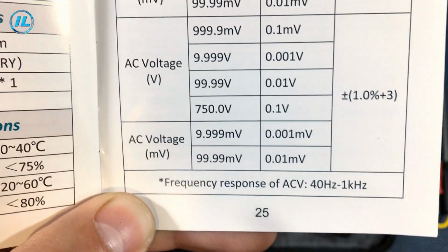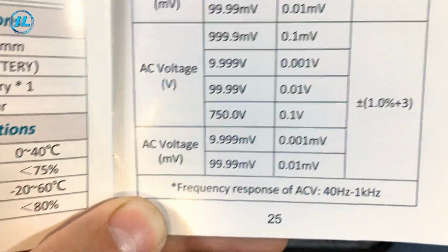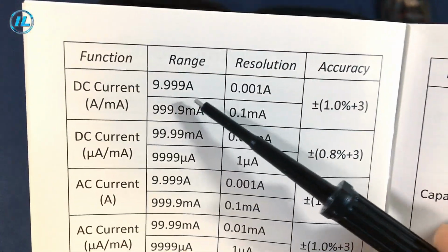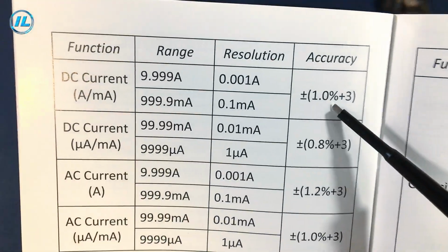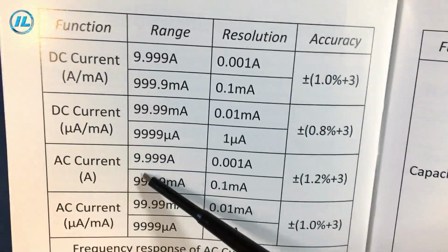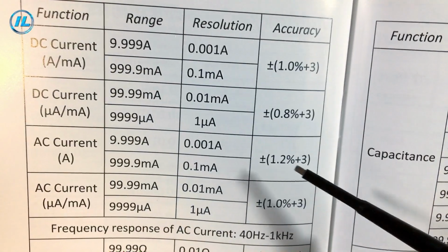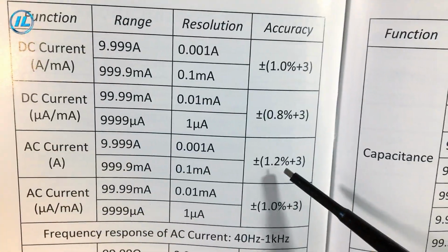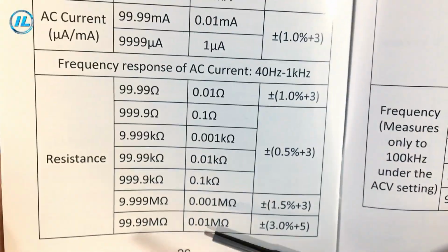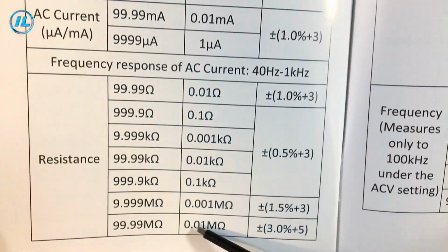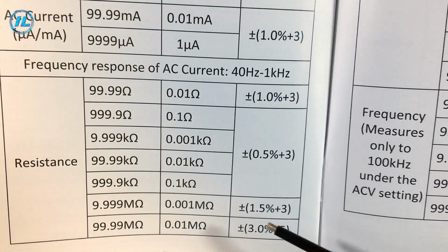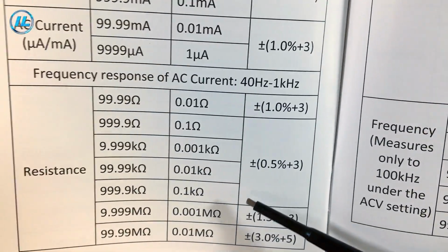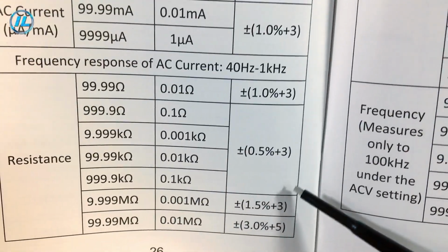Measurement of DC current up to 10 amps and an error of 1%. The measurement of alternating current is also up to 10 amps. And the error is slightly more, 1.2%. Next, the resistance measurement, up to 100 megohms. The margin of error is 3%. In the main range, the margin of error is 0.5%.